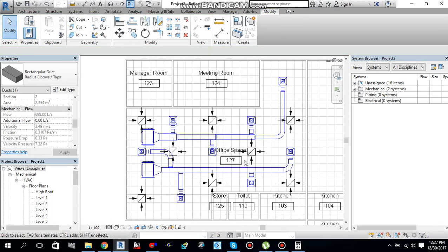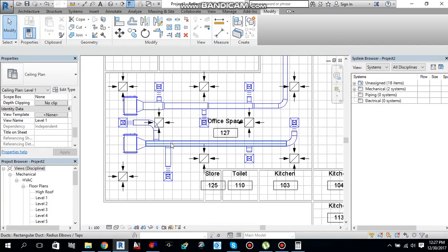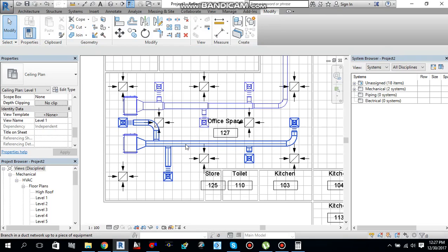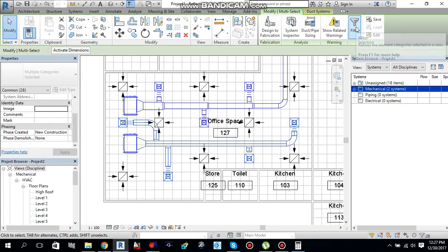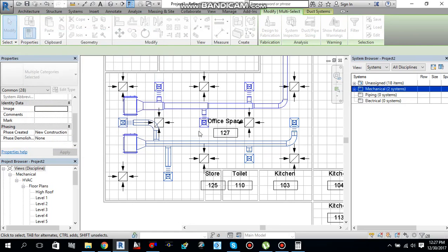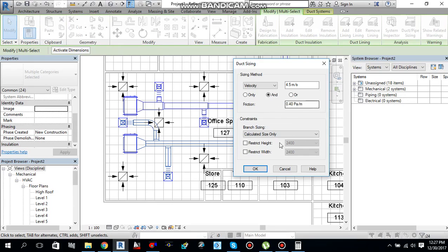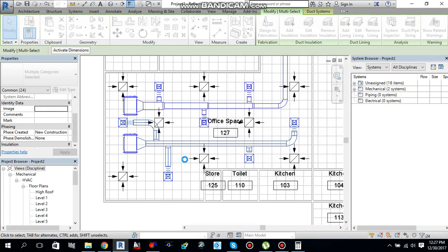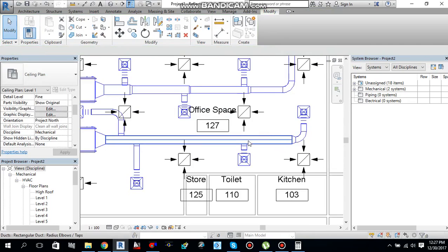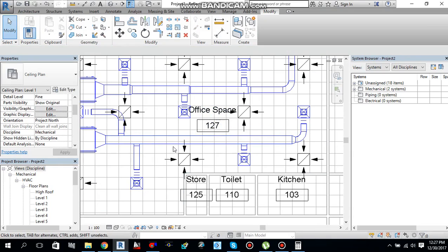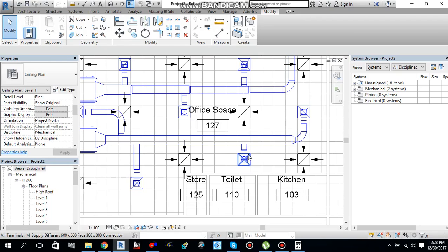Now applying the same method for the second machine. Hover the pointer over one of the ducts to highlight it, press Tab once then again to select ducts and diffusers, left-click to select, then go to Filter and uncheck Air Terminals, say OK. Again go to Duct/Pipe Sizing, velocity 4.5 maximum, friction 0.40 Pascal per meter, say OK. Done. Now I need to split this duct into different pieces after each branch.